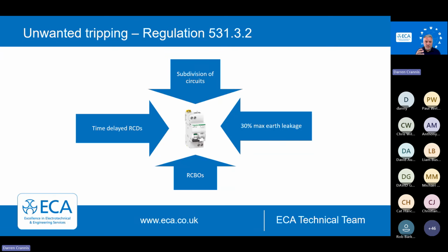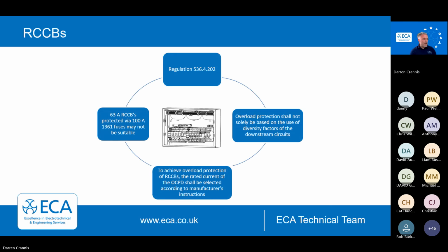And we can fit things, especially with the time delayed RCDs on our distribution circuits and our head ends. So there's those 500 milliamp RCDs, 300, 100 with time delays built in. We've been doing this with generators for decades to give that sort of fault protection. We can do that with our domestics and also our commercial installations too. Some people come to us and say that the split load boards are the devil and they can't be used, but they are still a perfectly good solution, heavily adopted by new house builders. And there is a UK specific regulation with these. They can still be used.